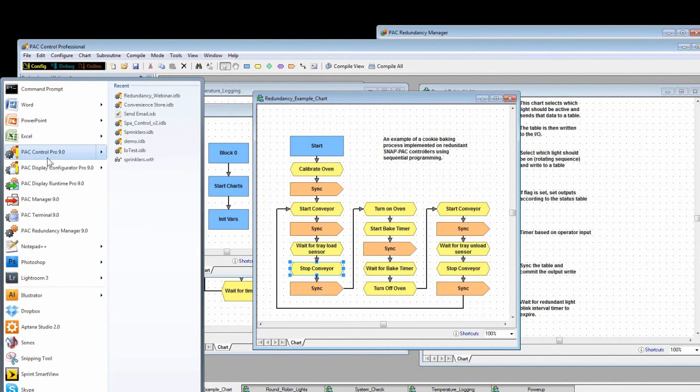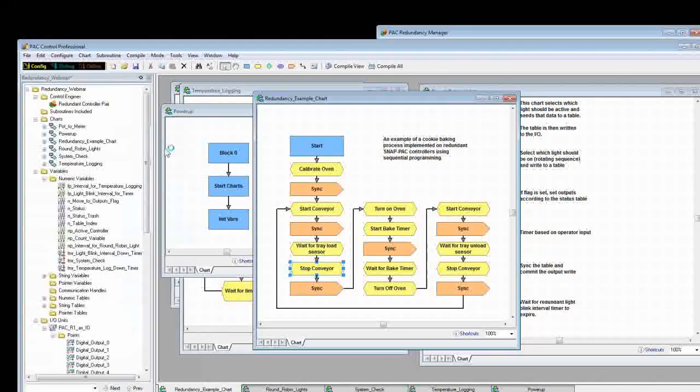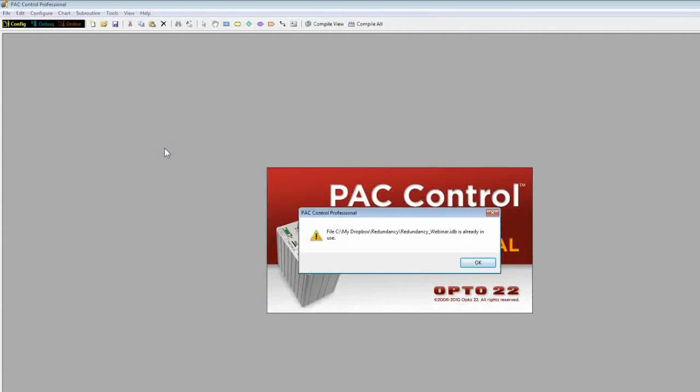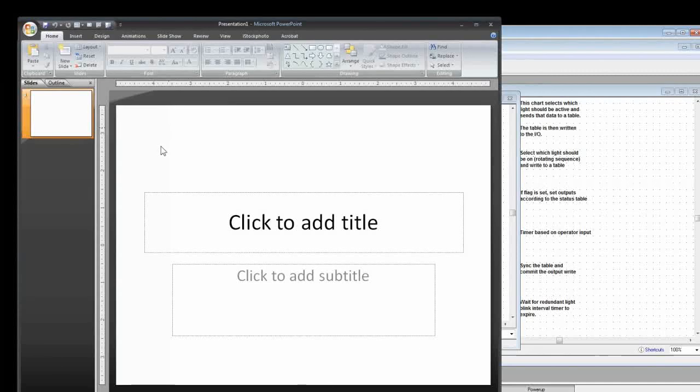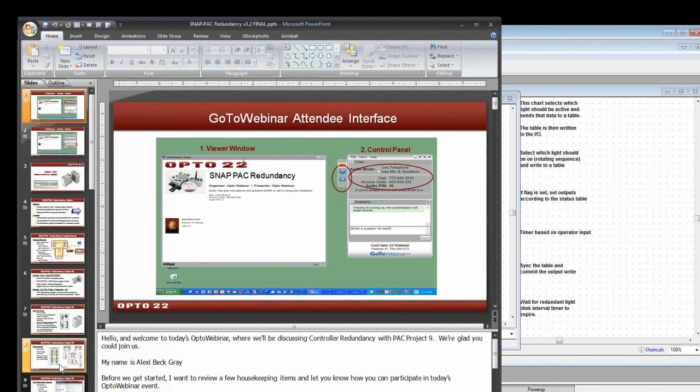And they're also connected on the network. I mean, right. Remember, it has two Ethernet ports. One Ethernet port is used for standard Ethernet connectivity. The second Ethernet port on the PAC S controllers is used for the sync network. Let me bring up the... While you're doing that, he's asking also, would you use a PAC S1 in a redundancy setup? And yes, you need a PAC S1 or S2 or S1 or 2 wireless controllers. As Benson said, the PAC-Rs are not supported as redundant controllers.